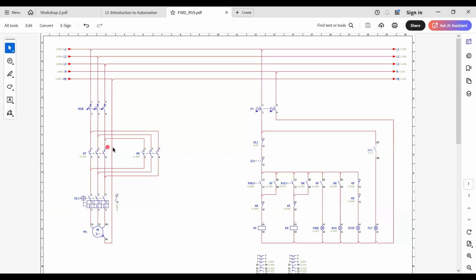Now let's see how this direction is changed. As you can see here, this L1 comes from here and it is connected to the W1 of the motor. L2 goes here and it is not changed. So the middle wire is not changed, right? You can see here it comes through here, again goes back the same as the forward contactor. But in the third one, the L3 comes here and it goes to the U1. So basically this wire and this wire are swapped in here to change the direction of the motor.